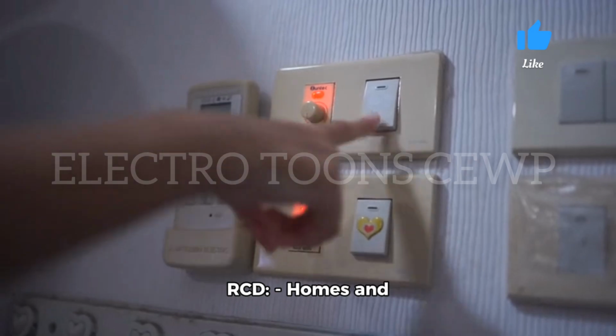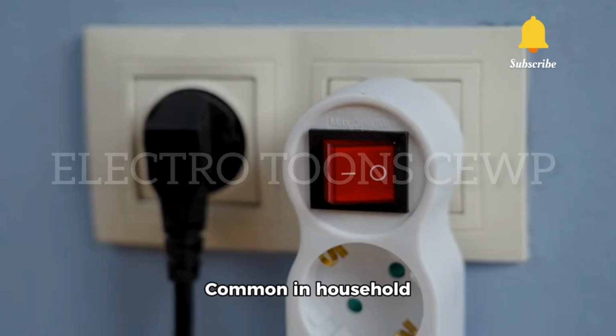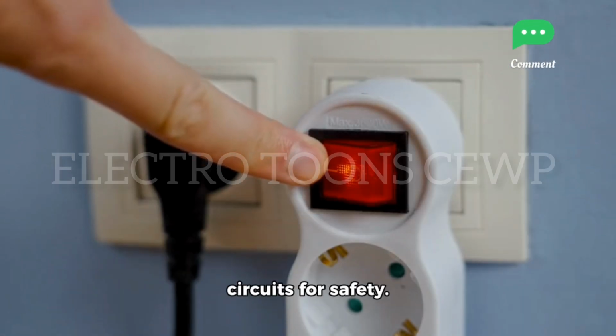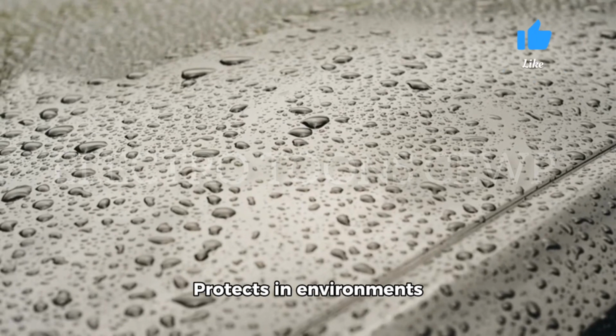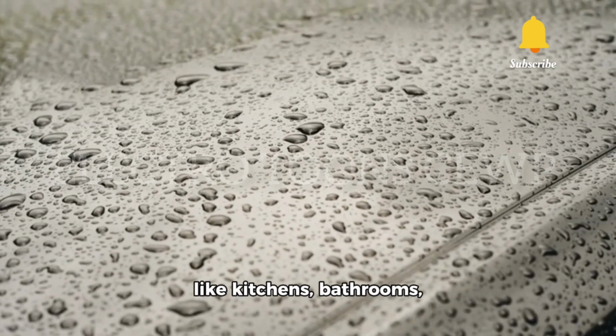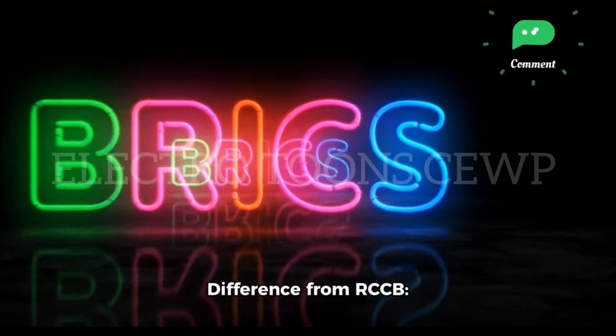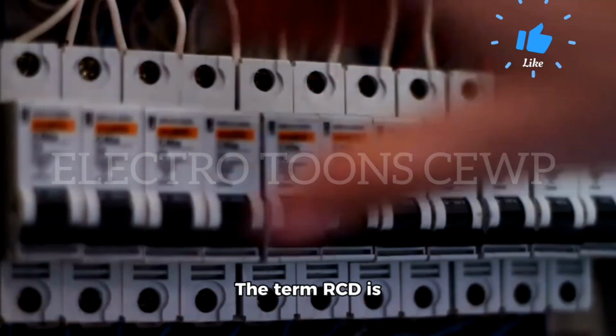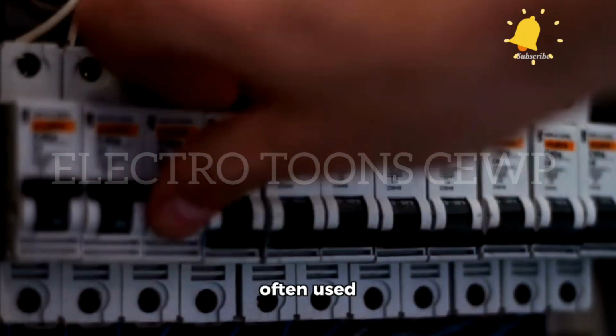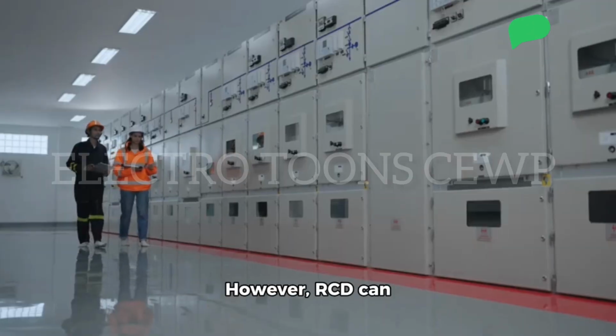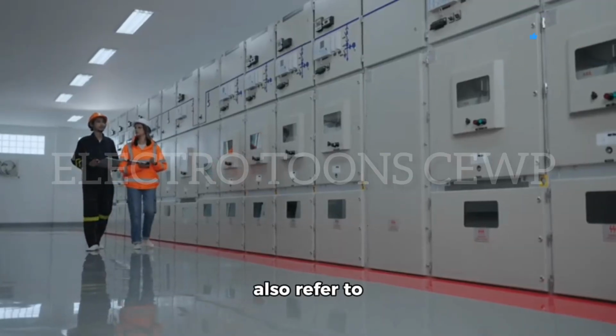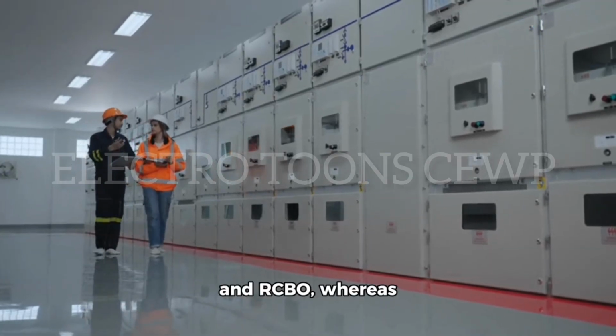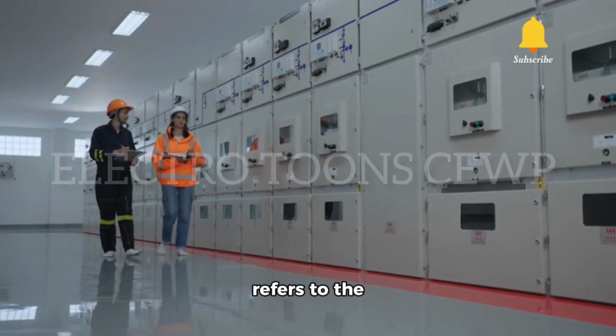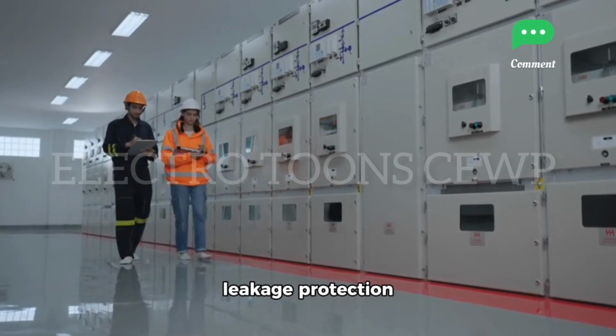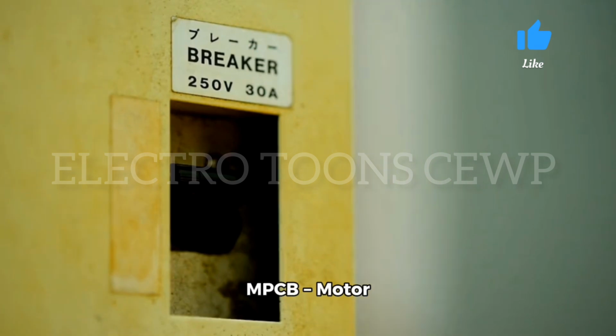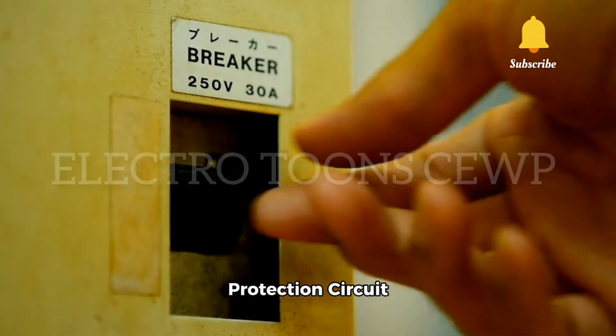Applications of RCD: homes and offices. Common in household circuits for safety. Wet environments: protects in environments like kitchens, bathrooms, and outdoor areas. Difference from RCCB. The term RCD is often used interchangeably with RCCB. However, RCD can also refer to devices like RCCB and RCBO, whereas RCCB specifically refers to the leakage protection without overload.